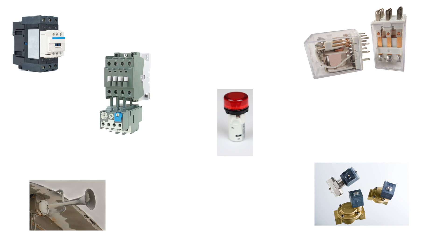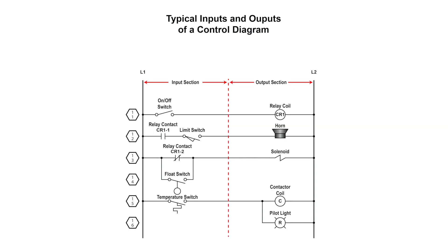Motor control circuits can have one or more inputs controlling one or more outputs. The example shows typical input and outputs of a control ladder diagram. The relay is energized once the switch is closed and will open CR12 and close CR11. The horn will energize once both the CR11 contact and limit switch are in the closed position. The solenoid is energized when CR12 or float switch are closed. Once the temperature reaches its set point and closes, the contactor will energize and close its contacts. At the same time, the pilot light will energize and turn on.